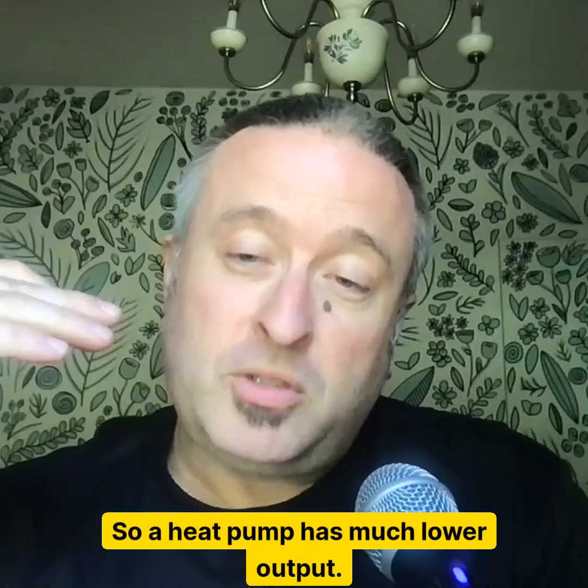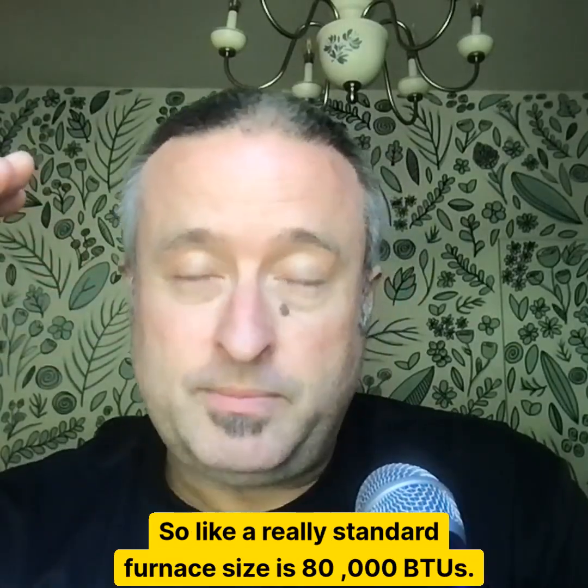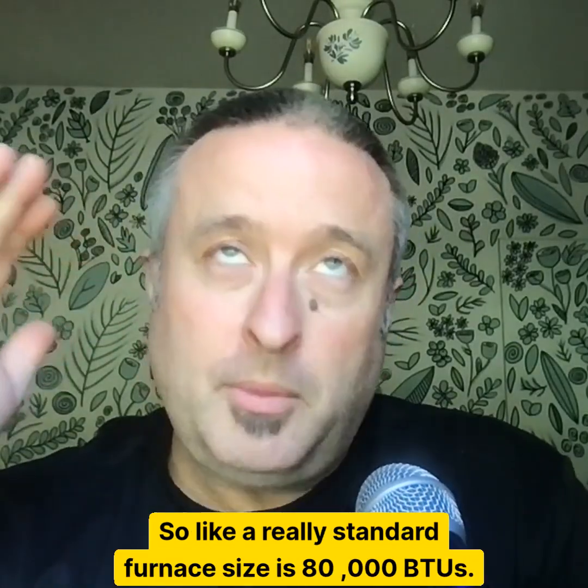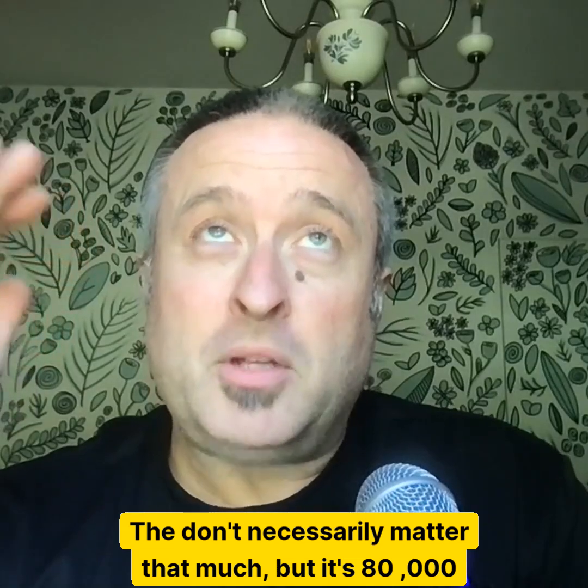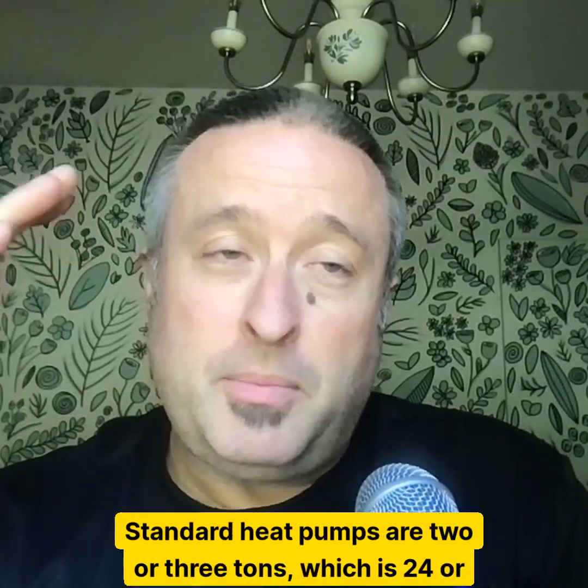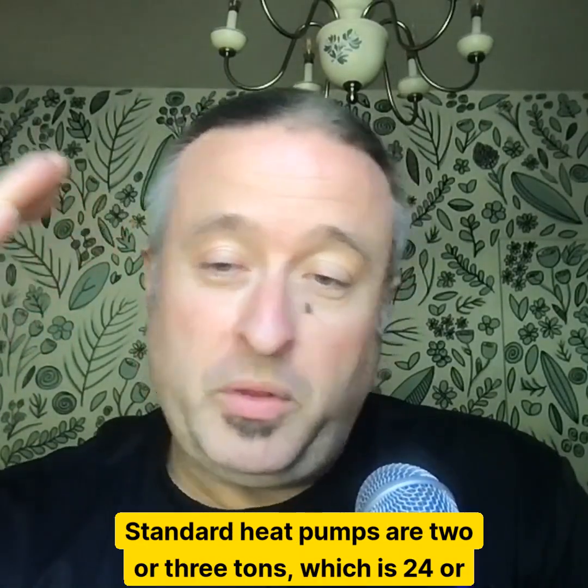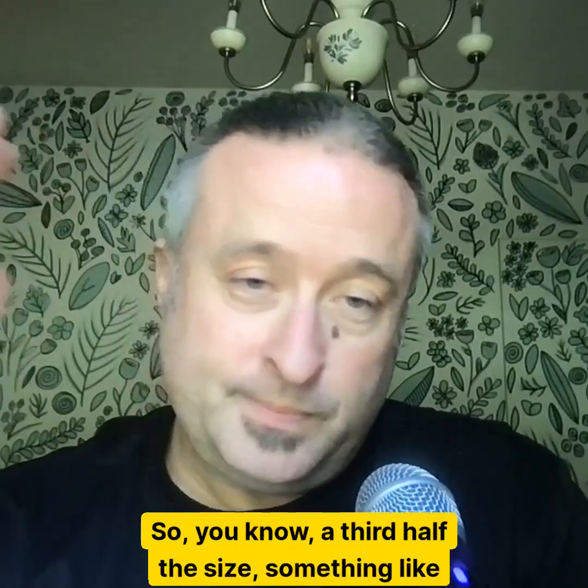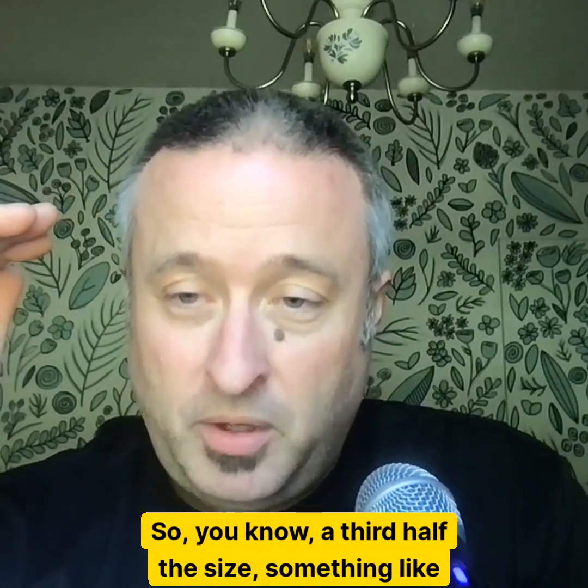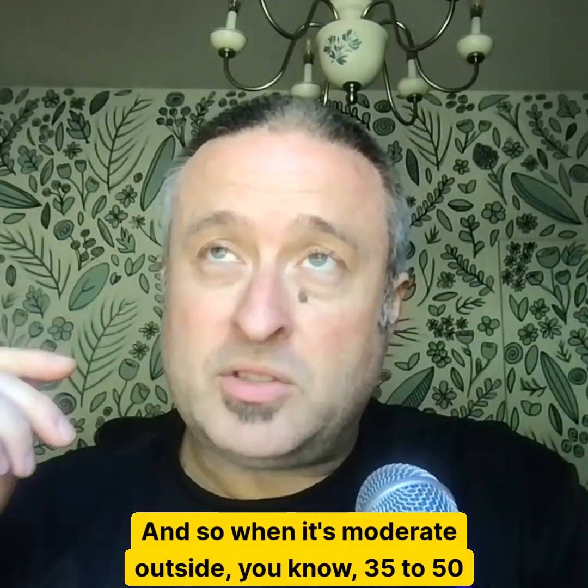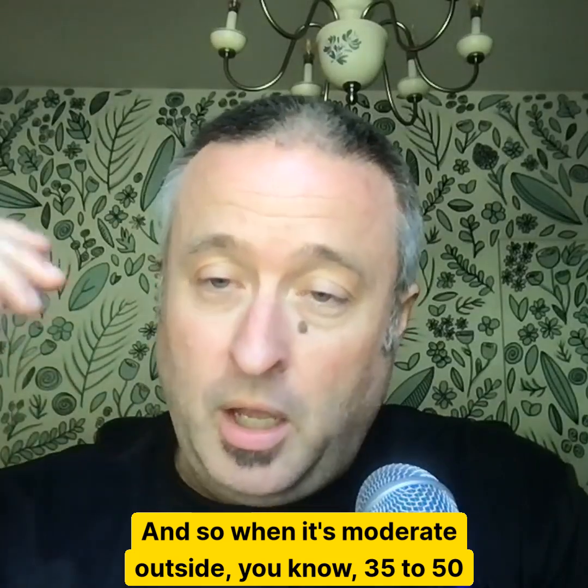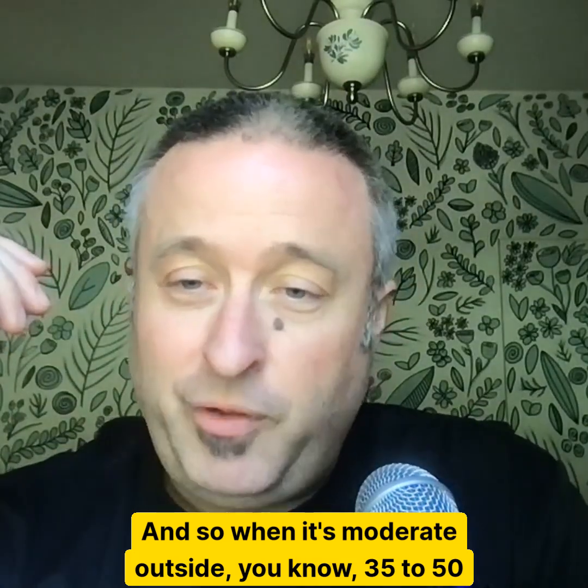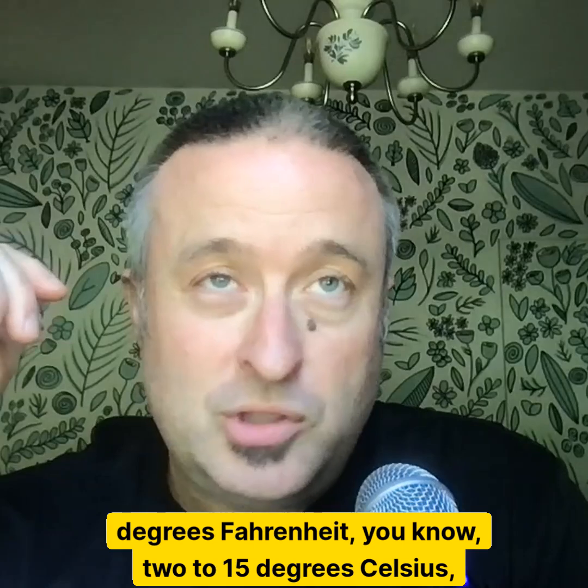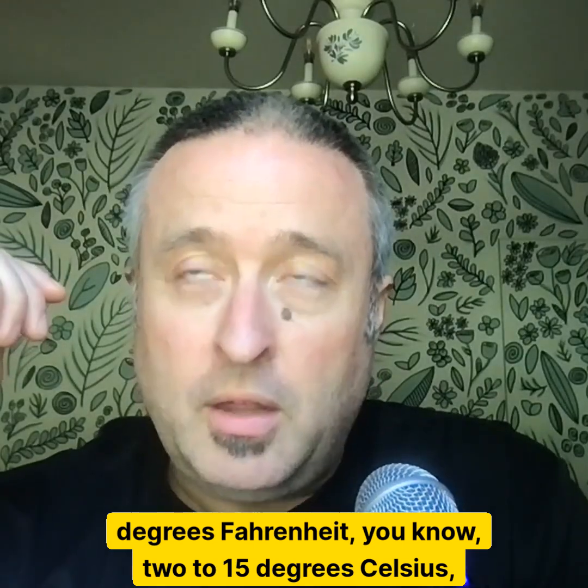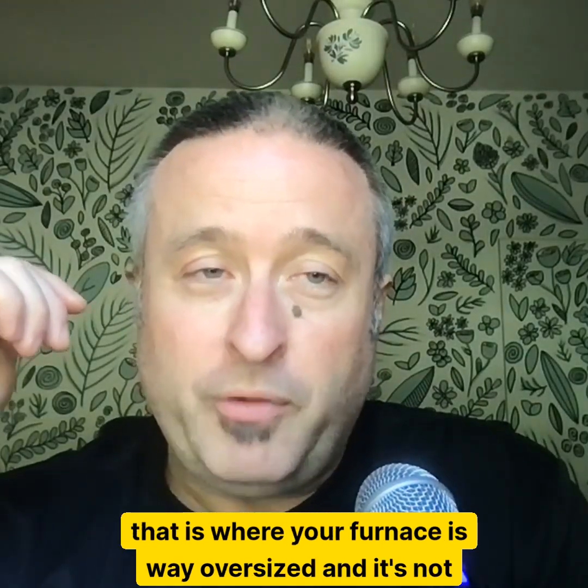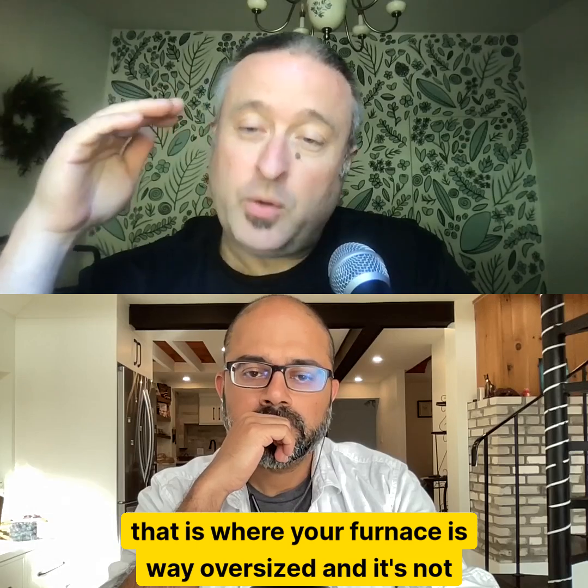So a heat pump has much lower output. A really standard furnace size is 80,000 BTUs. The numbers don't necessarily matter that much, but it's 80,000 for a furnace. Standard heat pumps are 2 or 3 tons, which is 24 or 36,000 BTUs. So, a third, half the size, something like that. And so when it's moderate outside, 35 to 50 degrees Fahrenheit, 2 to 15 degrees Celsius, that is where your furnace is way oversized and it's not going to make your house comfortable.